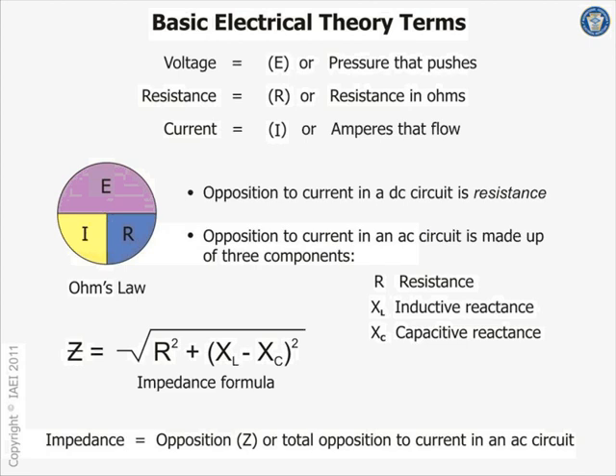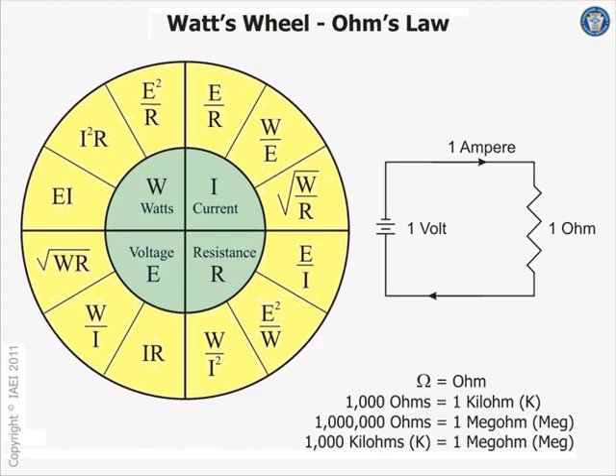So the R, and what is R? R is the material that you use. Copper: the bigger the conductor, the smaller the impedance. So you can control R easily, because you can always reduce R by pulling bigger conductors. That's why we have bigger control in the power system, by using bigger conductors. We can always size conductors bigger, and we have full control, like voltage drop. When it comes to voltage drop, 90% of the offender is the R. So how do we solve it? Size the conductors up. So we're good for up to 90% of the power system.